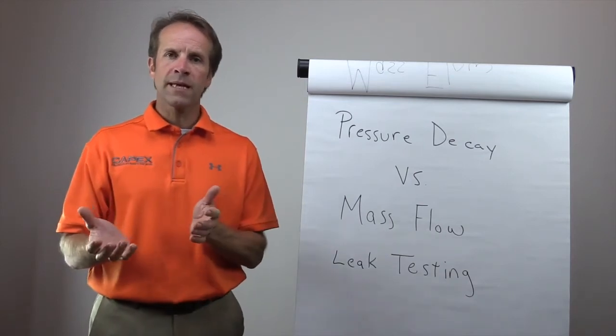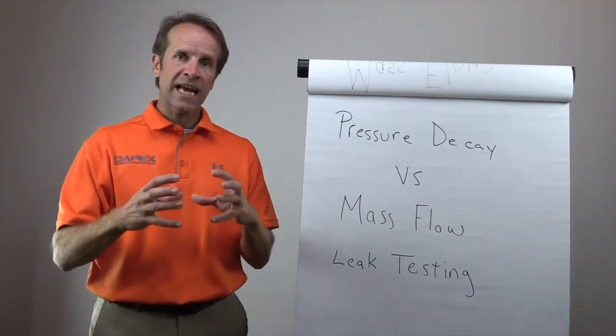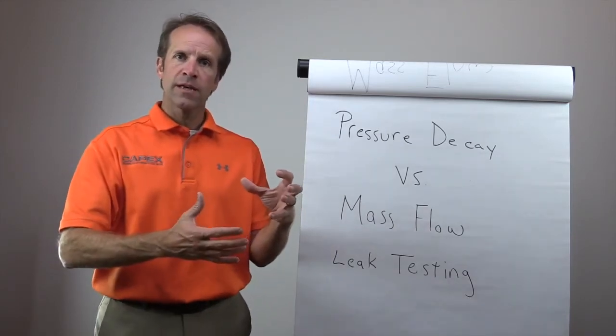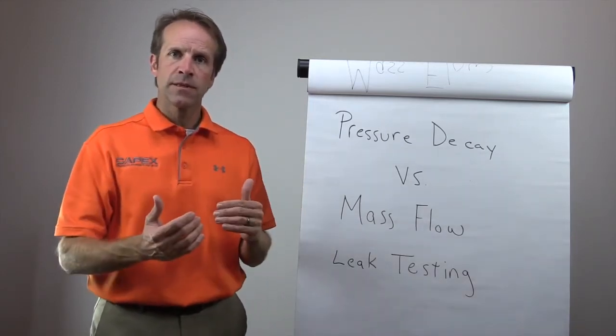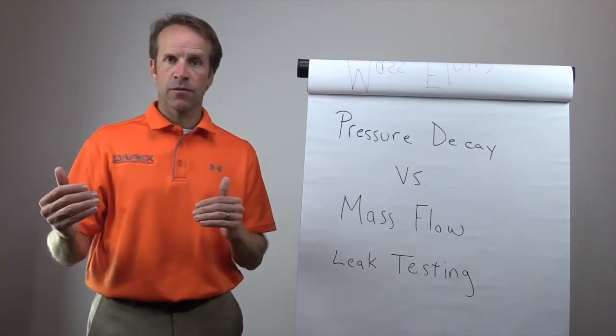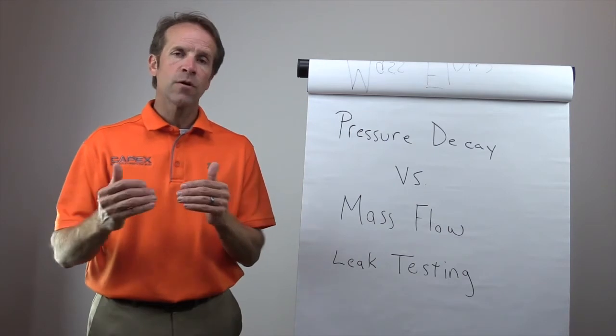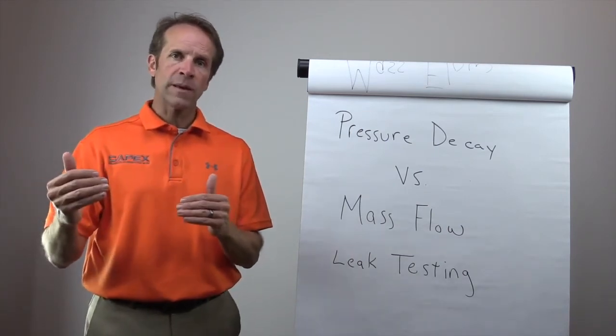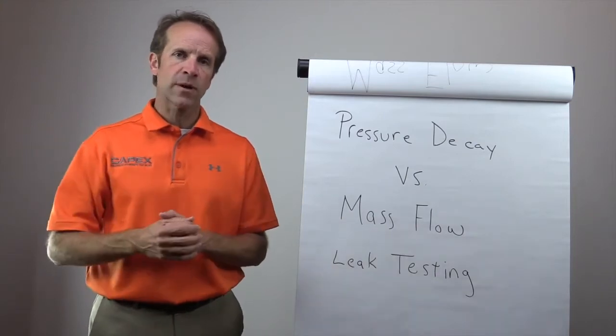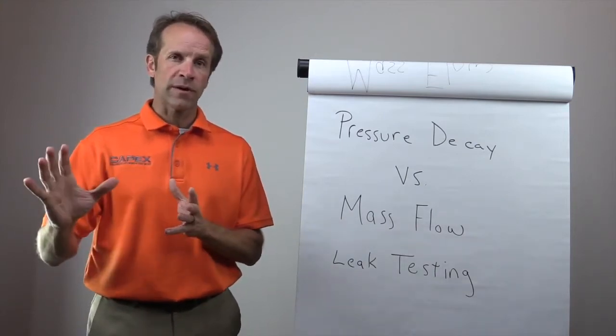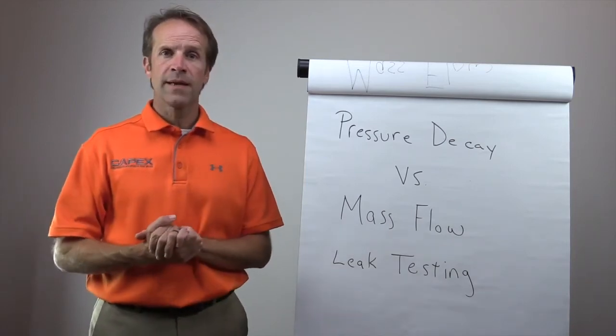Well, what does that mean compared to pressure decay? Well, pressure decay, we are isolating the circuit, right? So essentially, we're cutting the flow of air off, and we're measuring the degradation of pressure. With mass flow, we are not cutting the flow of air off to the part. We are continually flowing into the part through a flow meter and essentially balancing the pressure across that regulator. So when you don't have any flow going in, it's going to measure zero as a result.